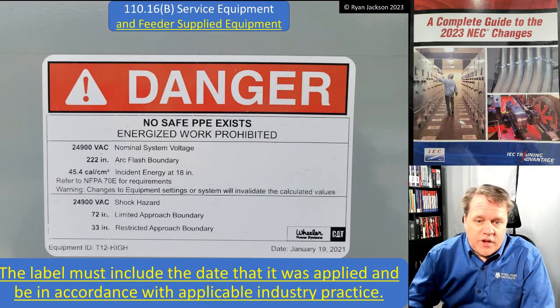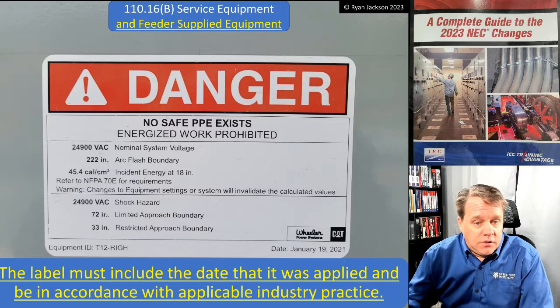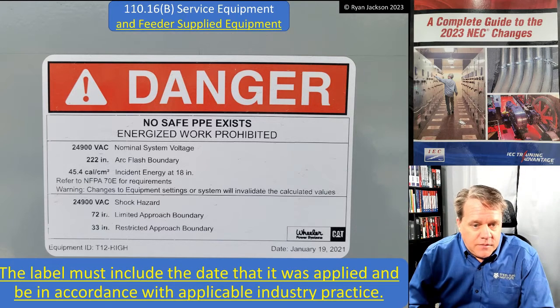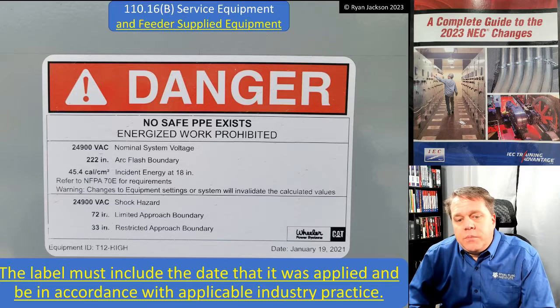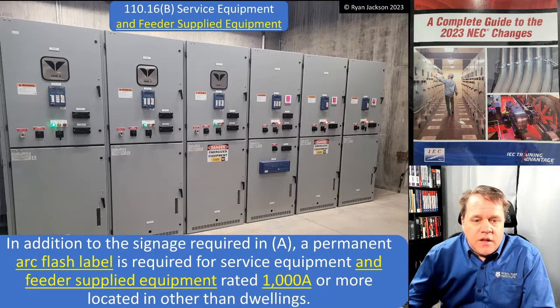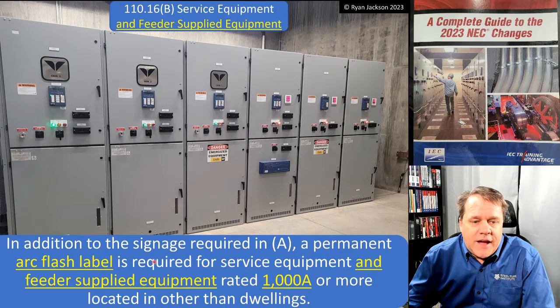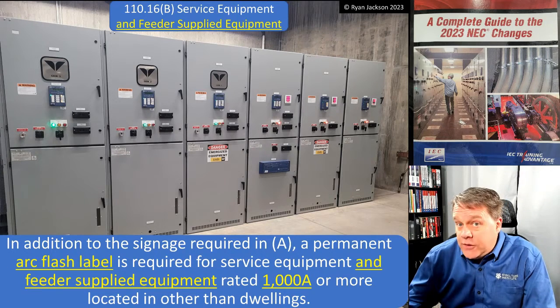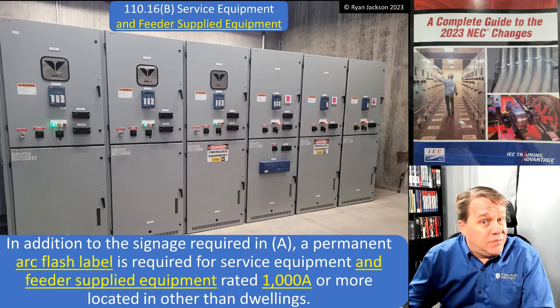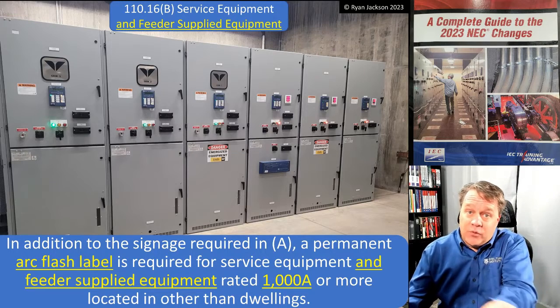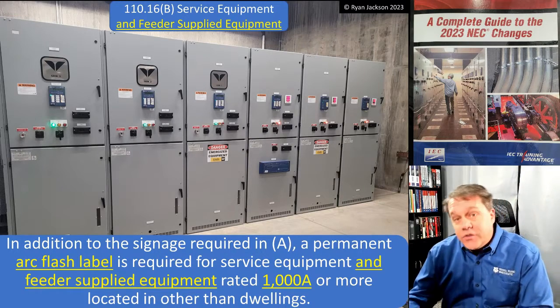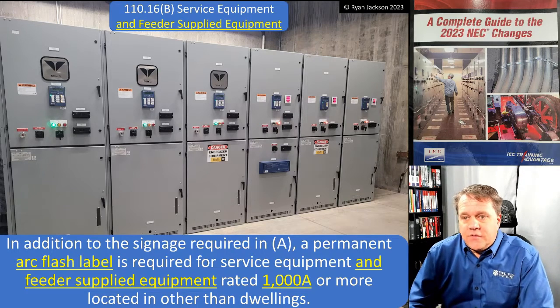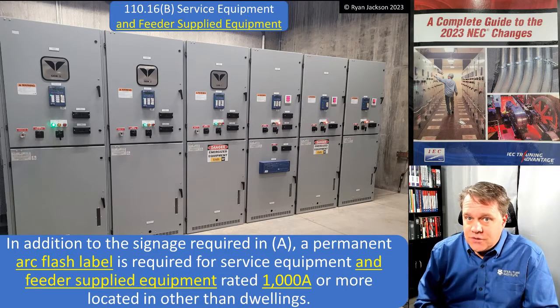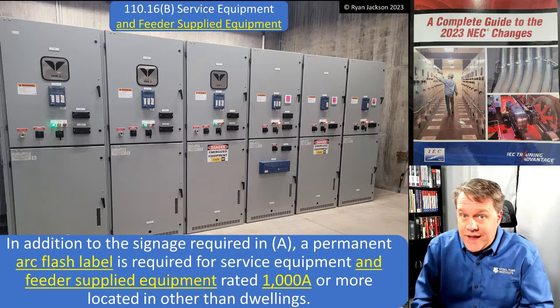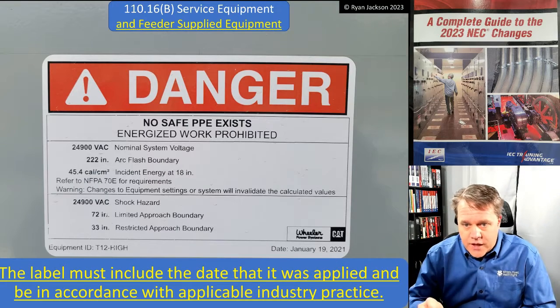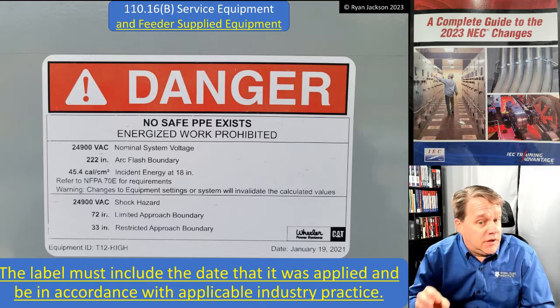Now, what is that other signage? Well, it says the label must include the date that it was applied, and it has to be in accordance with applicable industry practice. See, it says you have to have what? An arc flash label. Now, what's an arc flash label? That's something that probably ought to be defined. If we're going to tell people we have to have it, we can't not define it. What's an arc flash label? Well, it's more than just warning arc flash, right? I think. That's certainly the intent. Has to include the date. Has to be in accordance with applicable industry practice.